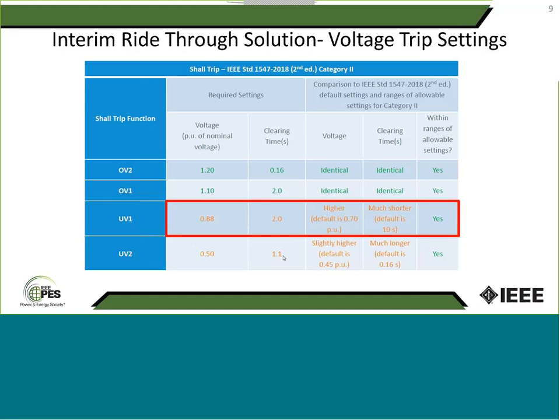So there's an issue here. Protection folks on the distribution side say, well, what if I have a fault on a distribution wire and your DER doesn't have overcurrent protection, so it's only relying on voltage to detect the fault, and now ride-through says it has to stay on for a certain period of time? But on the distribution side, we really don't allow that. We want generators and the utility source to trip off as fast as possible.